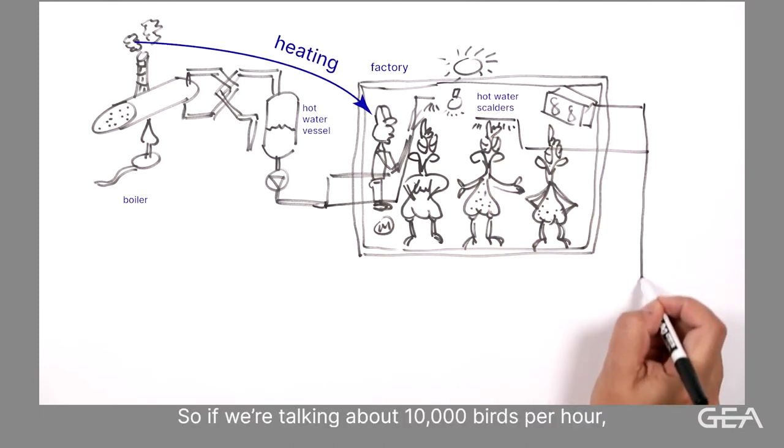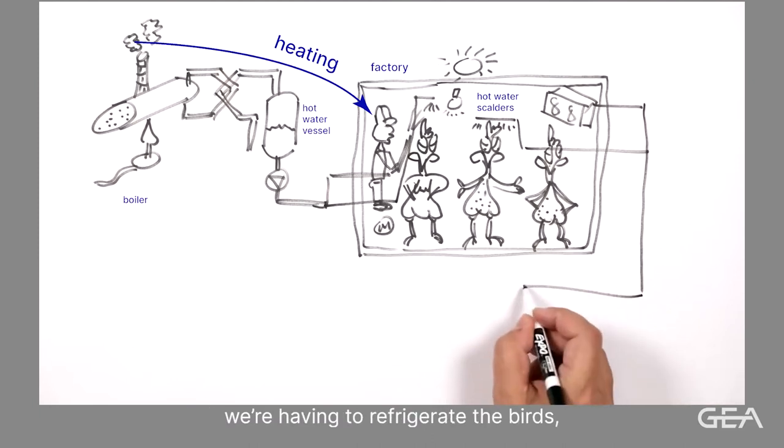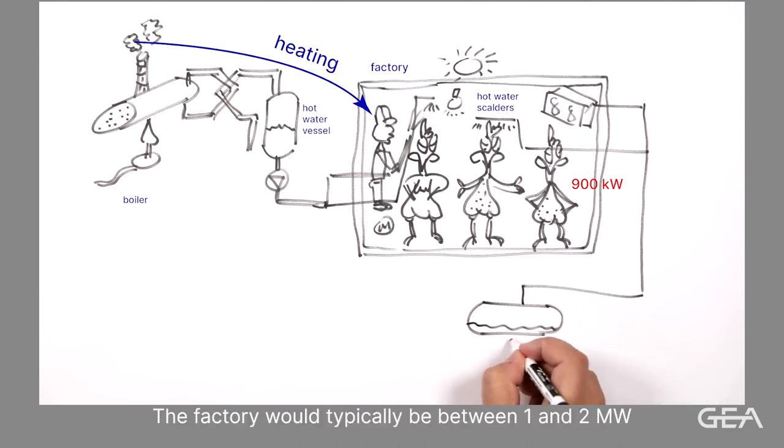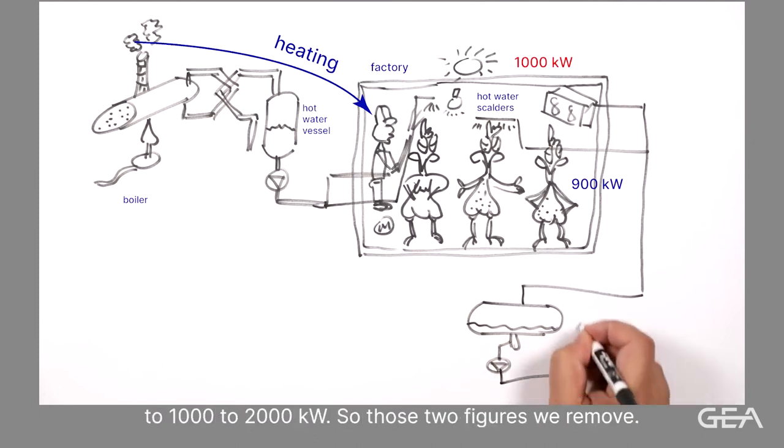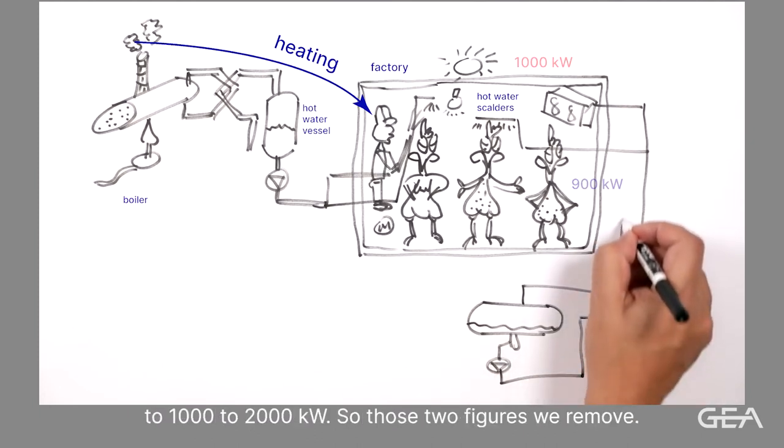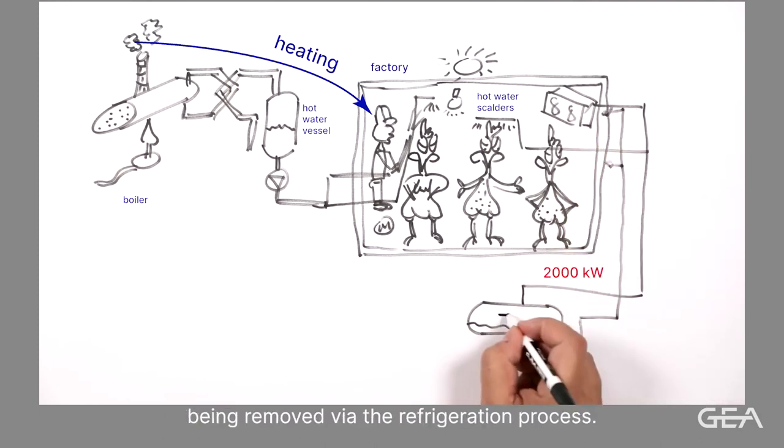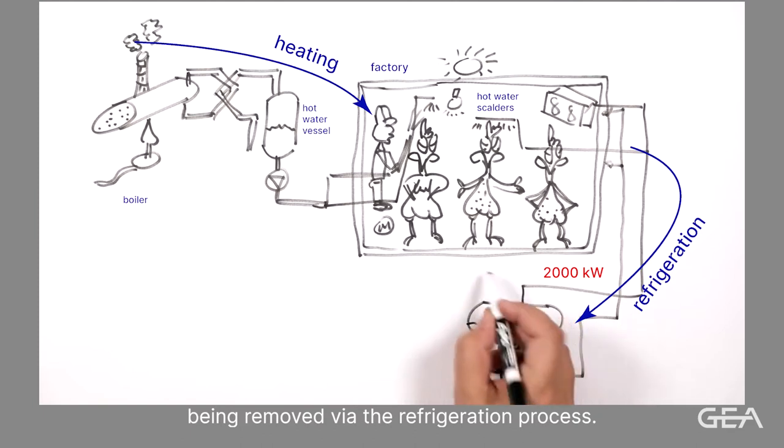So if we're talking about 10,000 birds per hour, we're having to refrigerate the birds. That's about 900 kilowatts worth of heat we have to remove. And the factory would typically be between 1 and 2 megawatts, 1,000 to 2,000 kilowatts. So now we have around about 2,000 kilowatts being removed via the refrigeration process.